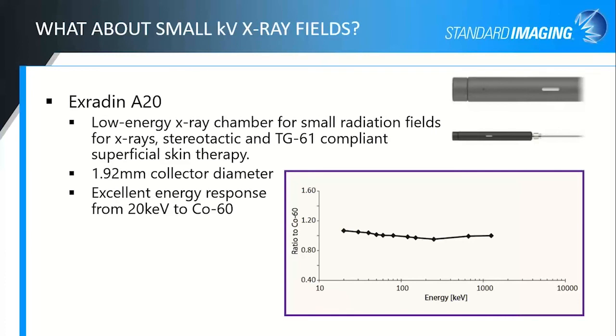I haven't talked about kilovoltage X-ray fields. That was all megavoltage we were looking at beforehand, but I do want to touch just briefly on small fields that are kV X-ray fields. We have a very small parallel plate chamber that's designed, again, in the end-on orientation, a little bit like our scanning diode. So your beam should be coming in this way, aimed at the chamber, but it's called the Exradin A20. And it's a low energy X-ray chamber that was specifically designed for small radiation fields that are kV X-rays, stereotactic fields, and TG61 compliant superficial skin therapy measurements. So it has just under a 2 millimeter collection diameter, and it has excellent energy response across the range of kilovoltage energies from 20 keV all the way up to cobalt 60.